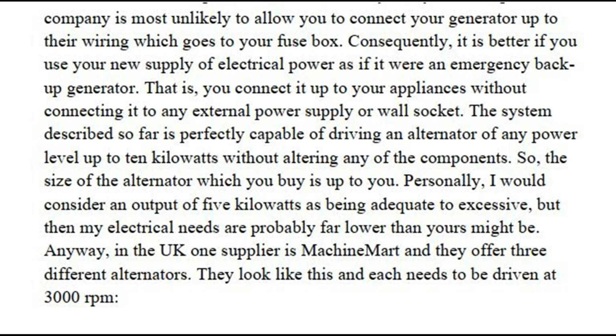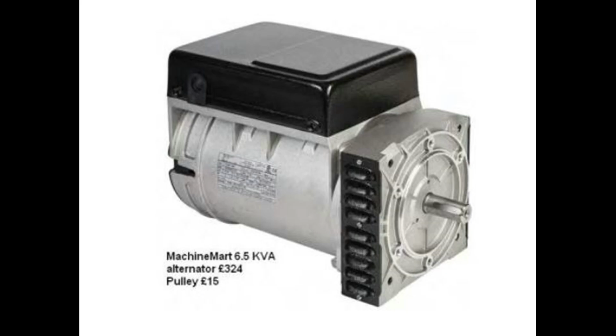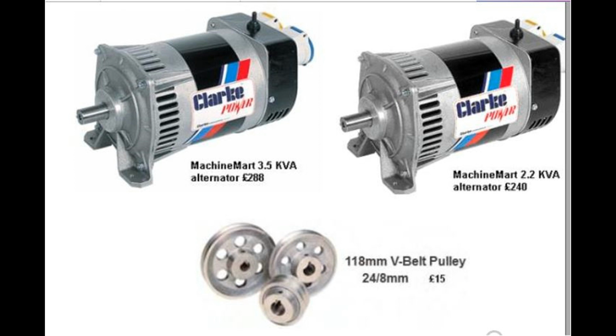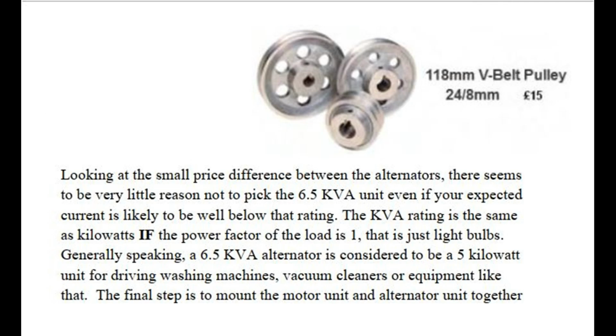In the UK, one supplier is Machine Mart, and they offer 3 different alternators, each needing to be driven at 3000 RPM. Looking at the small price difference between them, there seems little reason not to pick the 6.5 kVA unit, even if your expected current is likely to be well below that rating. The kVA rating equals kilowatts only if the power factor of the load is 1, as with light bulbs. Generally, a 6.5 kVA alternator is considered a 5 kilowatt unit for driving washing machines, vacuum cleaners, or similar equipment.